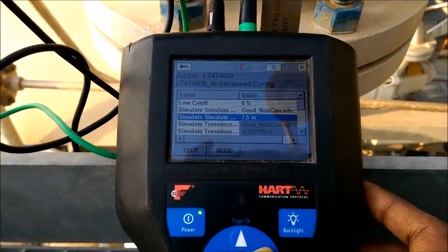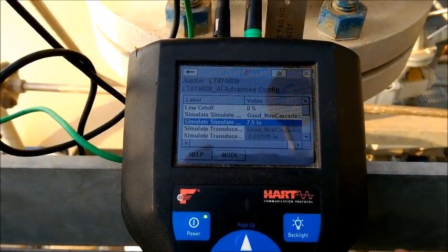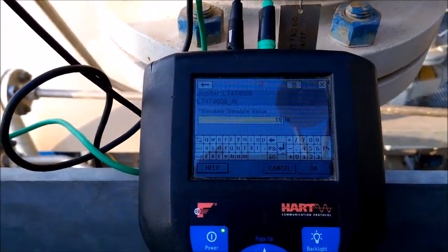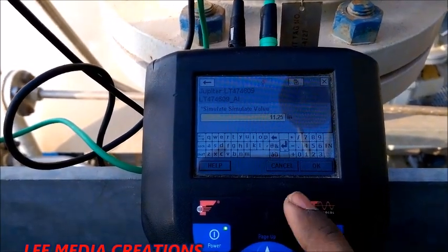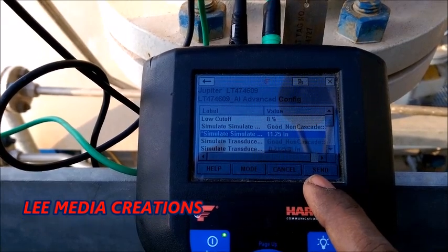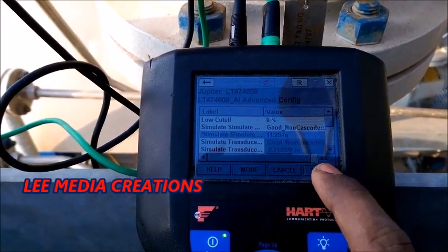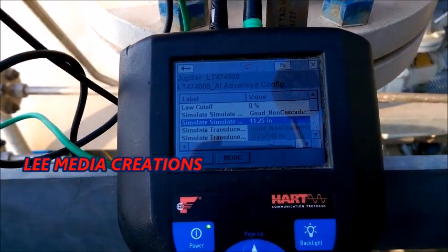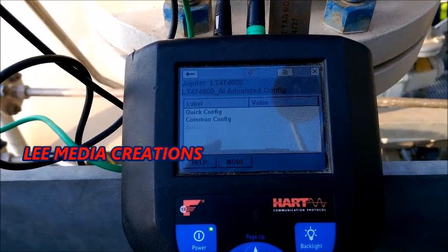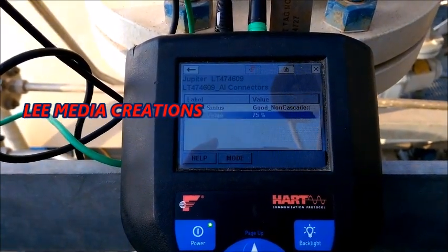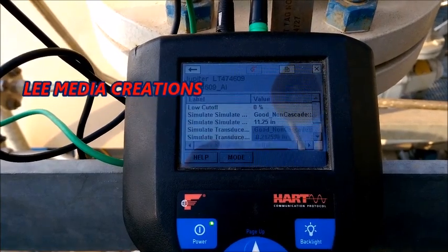Now I want to apply 75 percent — that is 11.25 inches. Click OK for 75 percent and click send. It is showing 75 percent in the DCS room. You can confirm that value.